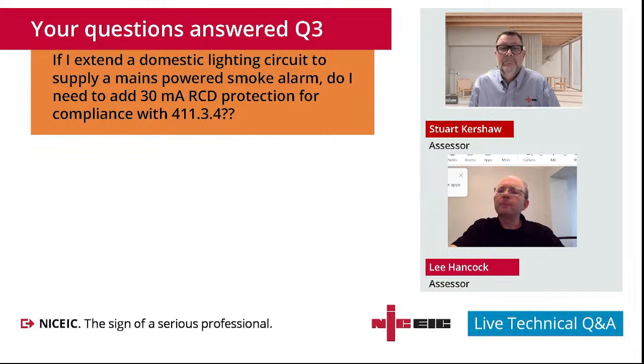We'll take another one that was held over, and again, quite a common question that we do get asked. If someone's extending a domestic lighting circuit to supply a mains powered smoke alarm, which is permitted, do they need to add 30 milliamp RCD protection for compliance with 411.3.4? I think this question boils down to a fairly recent change: domestic lighting circuits now require RCD protection. So someone's come across a lighting circuit that doesn't have RCD protection and is extending it to power a mains powered smoke alarm. Do they need to provide RCD protection for compliance with the 411.3.4 regulation? I think Stuart is going to help us with this one.